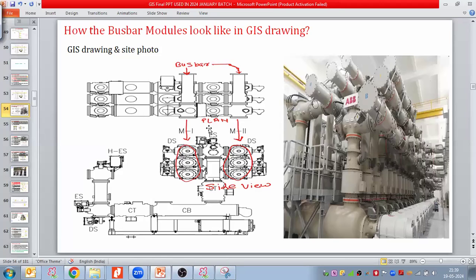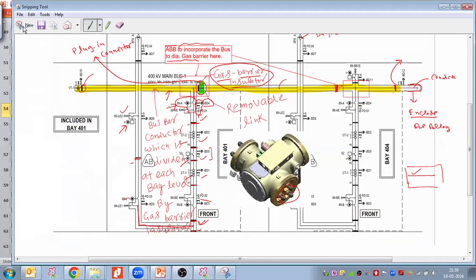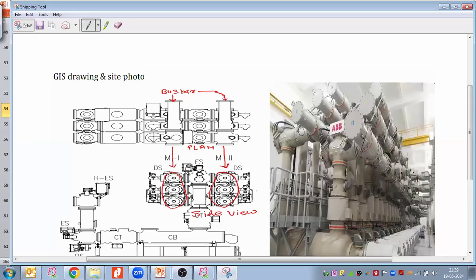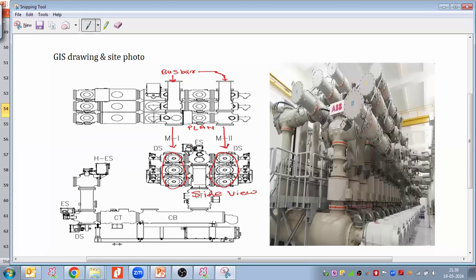First of all, you should know how to read the drawing, and how to interpret and understand each and every equipment module. Generally, if there is any kind of confusion, or for site practice as well, when you take the drawing, you can ask the GIS manufacturer or supplier to do the marking on each module. Like if you see here, I have asked for the marking of each equipment module. So they have marked here: this portion indicates the breaker, this portion indicates the CT, earthing switch, disconnector, high speed earthing switch, disconnectors. Like that, you can also ask your manufacturer to do the marking as well.